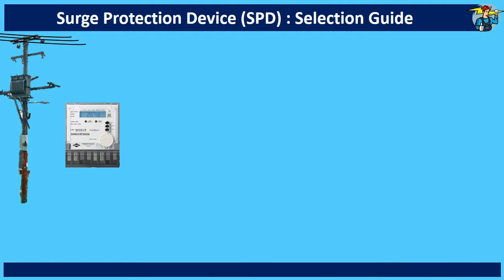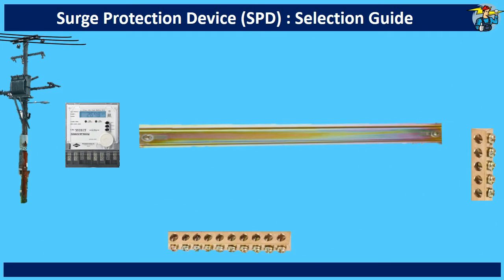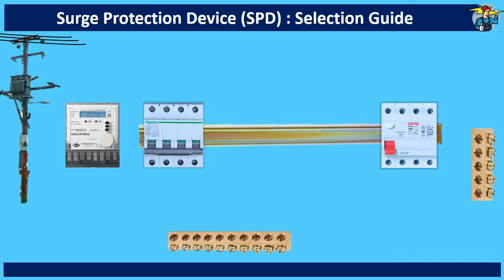First, let's see how the panel board near the entrance is wired. For the distribution board, you need a four-pole main circuit breaker, and a residual current device — that is RCD — which is commonly known as the trip switch. Although I have shown this for a three-phase system, selection and installation of an SPD for a single-phase system is not much different.